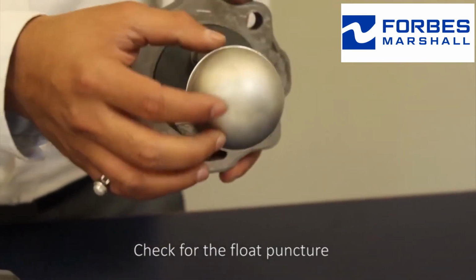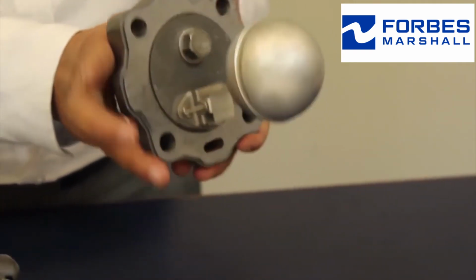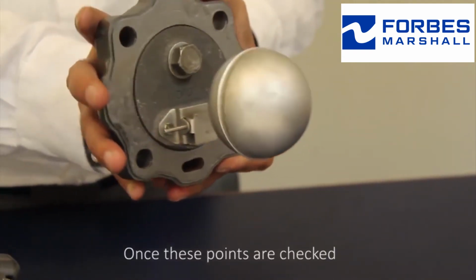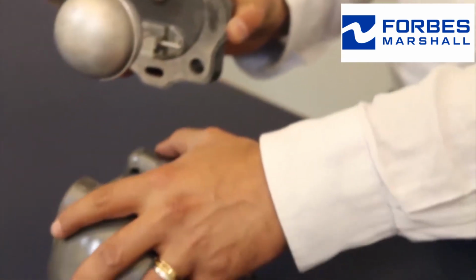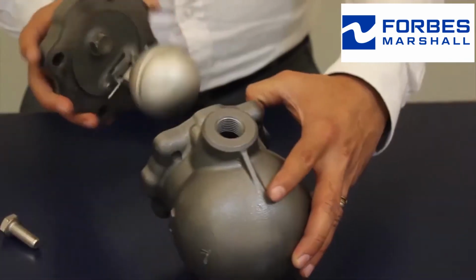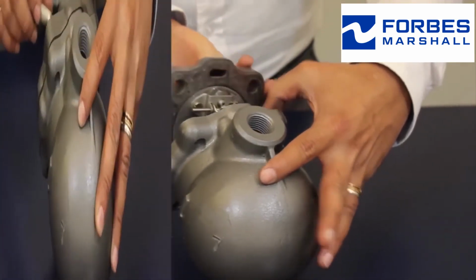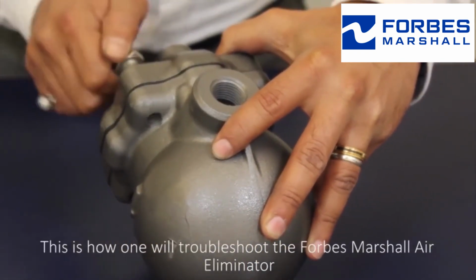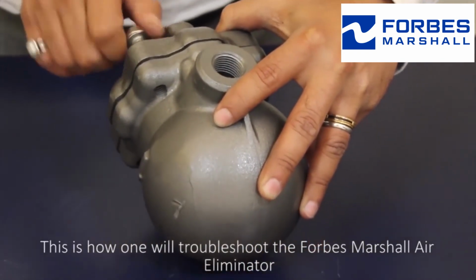Check for the float puncture. Once these points are checked, reassemble the trap. This is how one troubleshoots the Forbes Marshall Air Eliminator.